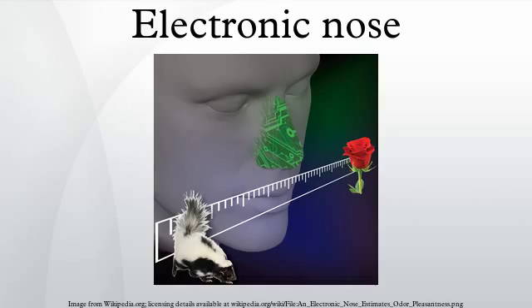The detection system, which consists of a sensor set, is the reactive part of the instrument. When in contact with volatile compounds, the sensors react, which means they experience a change of electrical properties. In most electronic noses, each sensor is sensitive to all volatile molecules but each in their specific way.